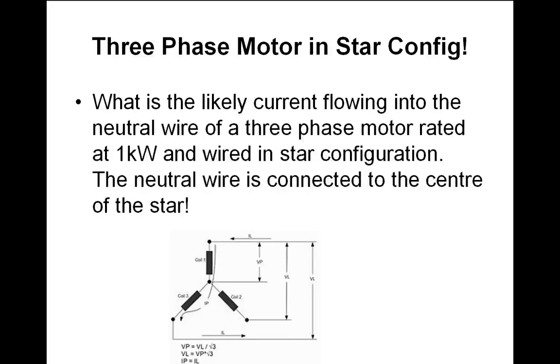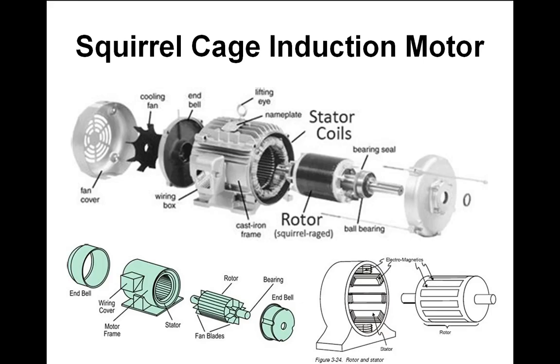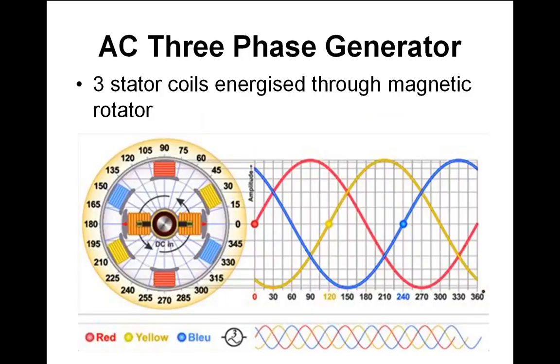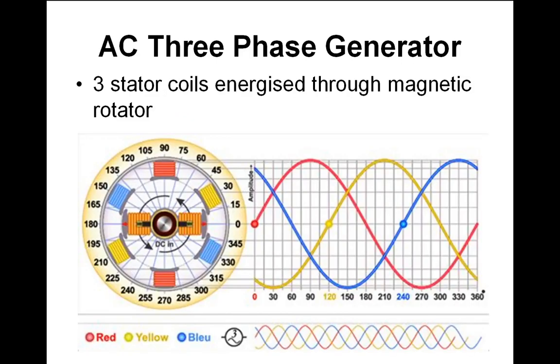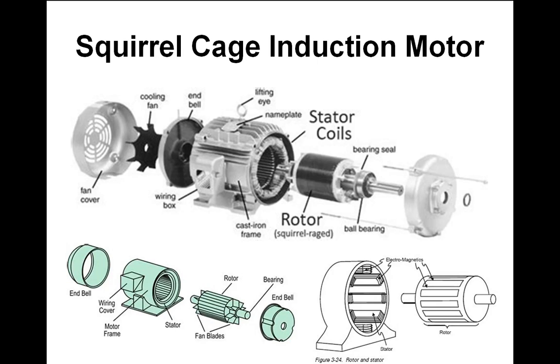Going back over synchronous versus asynchronous: an asynchronous motor has no slip rings — just a bearing and a squirrel cage with no electrical connection, only mechanical. No sparks, no arcs, no carbon brushes. A synchronous wound rotor motor has a coil on the rotor with a DC supply fed in. The rotor is swung round by the orbiting magnetic field from the three-phase stator.